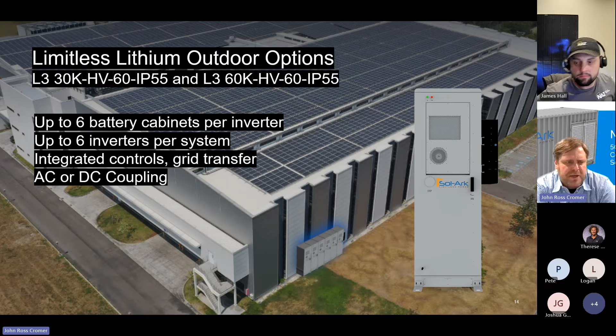So the outdoor cabinet is very space efficient. Our inverters are outdoor rated, so we don't need to put them inside the cabinet, where you would have an air conditioned cabinet and then the inverter generating a ton of heat. Instead, we just air condition the batteries. That means it's a very efficient cooling system. The inverter hangs off the side of the cabinet. The cabinets can be bolted to the foundation. They can be grabbed with a forklift on either side and set in place.